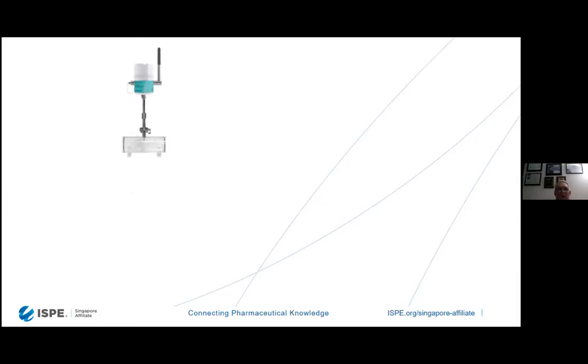Typically, a rouge monitor has three different parts. First part is the transmitter and the probe. The probe, as you can see, is installed here showing a clear plastic pipe, but only the probes are down there. There's a 1.5 inch flange that runs on an adapter up to the bottom part of a transmitter, providing the power at 24 volts. And then there is a transmitter up on the top that sends the information wirelessly to a gateway. And that gateway itself can encompass many, many of these different devices, from 1 unit up to 60 units out in the field.